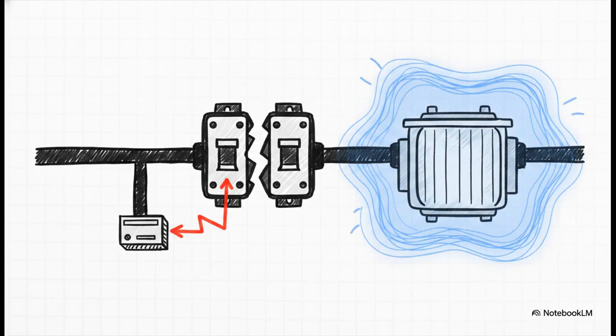Now, once those mechanical contacts close in stage 4, the relay completes a circuit that essentially commands the main circuit breaker to activate. Modern circuit breakers receive that signal and fully open within 50 to 100 milliseconds. That completely isolates the faulted transformer from the power source right before structural failure becomes inevitable.